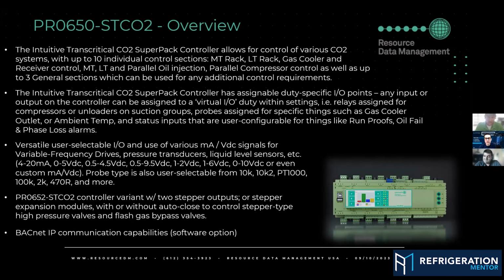Very cool. Can I touch base real quick, while we're going over the controller, the STCO2 and controllers in general? I do want to make this pretty clear. This is what I like about RDM from the controller standpoint. It's simplified. The flexible combiners and running math and building all this in the background, that's all gone away. This is changing a couple of things around, moving some mapping around, and doing some real simplified stuff. So once you get to know it and get familiar with it, it's very simplified in troubleshooting and changing some stuff around, instead of spending 2 or 3 days rebuilding the whole flexible combiner on a rack. You know what I mean? So this is way more simplified on that aspect of things.